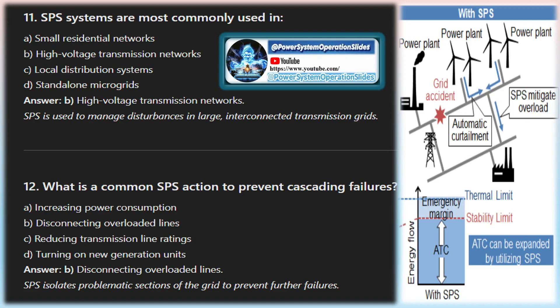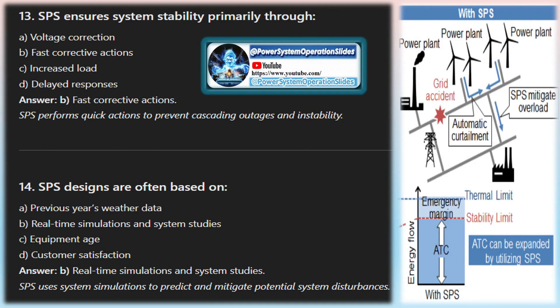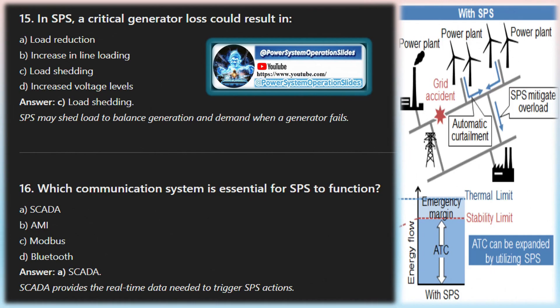In a context of restrained network development and more intensive use of available generation and transmission facilities, the implementation of special protection schemes might increase in future. If a TSO relies on special protection schemes to meet specified power system performance levels, these schemes must be highly reliable — protection-grade reliability is required — with proper redundancy of the SPS elements. The application of special protection schemes might have local, regional, or over-regional impacts, and where there is influence on neighboring TSOs, the realization of special protection schemes must be coordinated between the affected TSOs. The design process includes: system study, solution development, design and implementation, commissioning and periodic testing, and training and documentation.